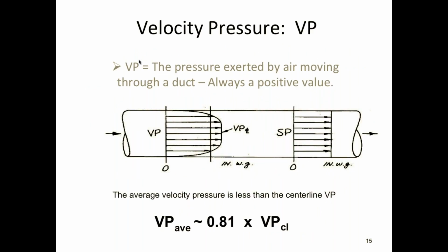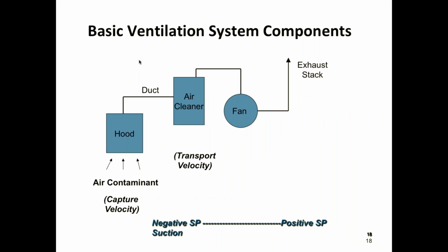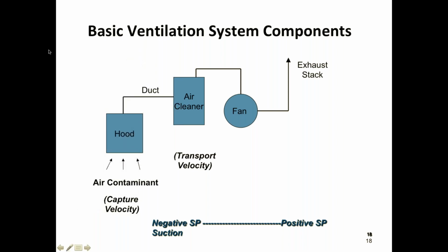Okay, so let's take a look at air moving through a duct, because almost all ventilation systems are going to wind up consisting of a hood, a place where you're going to capture the material. I've got one over here somewhere, like this. This could be a lab hood with the glass that comes up and down. That's a hood. The point at which you're doing the capture could be considered a hood, right? It typically also has an air cleaner, because usually if it's something you don't want to expose the worker to, you don't want to expose anybody else to it, so you have to take it out of the air.